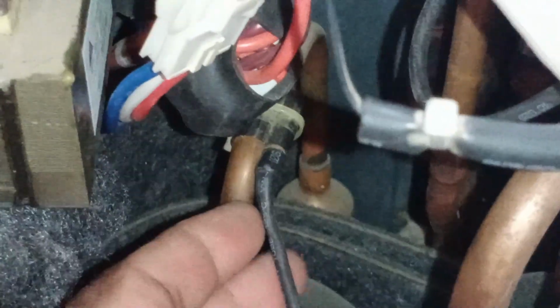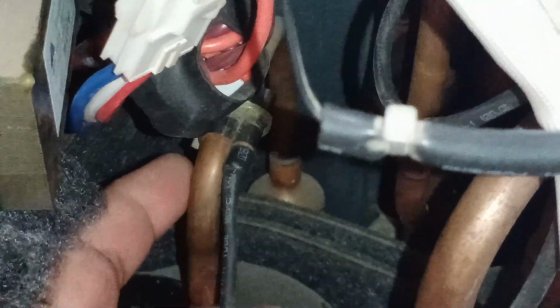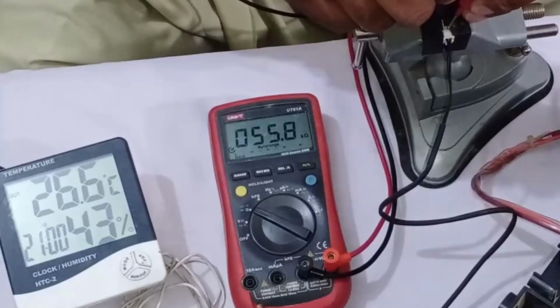If this sensor falls off from its position, notice that it is secured with a cable tie. Then due to it getting disconnected or broken, the system will display error code 2. This happens because the feedback signal is no longer reaching the microcontroller, causing the unit to detect a fault. The resistance value of this thermistor is 55.8 kiloohms.